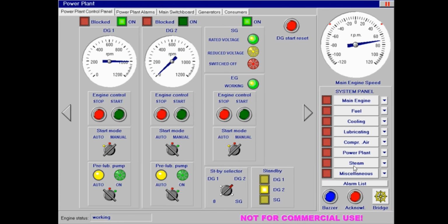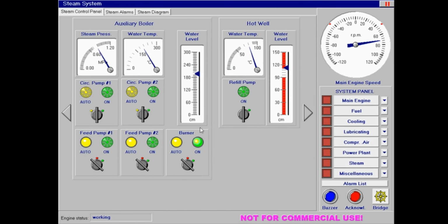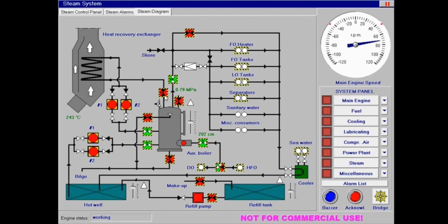So this is a good time to go on steam system. Here, turn on our two circulating pumps. It actually starts circulating some of this water out into the exhaust funnel to heat up the back end heaters so that we can save our steam. By the way, while we're here, we can always click this button to flip to using the heavy fuel oil as our source of fuel, which I say is safe for the boiler. It's kind of nice.